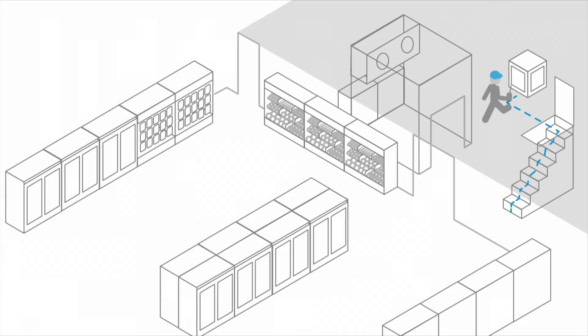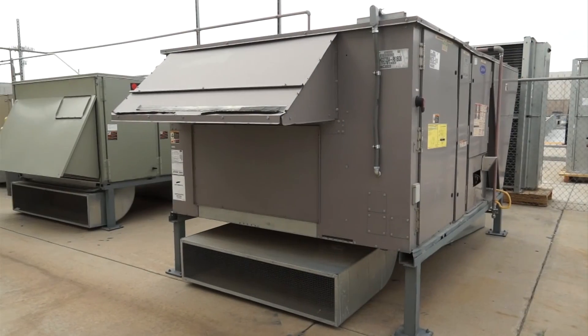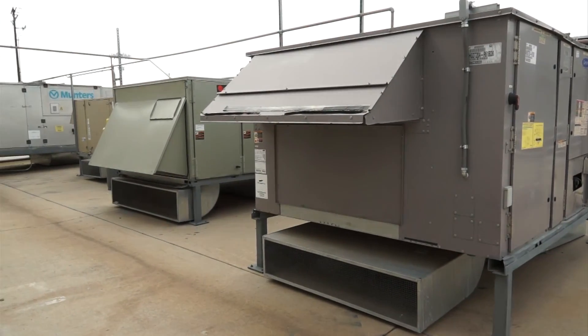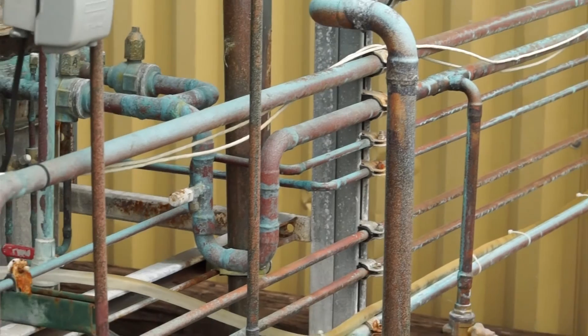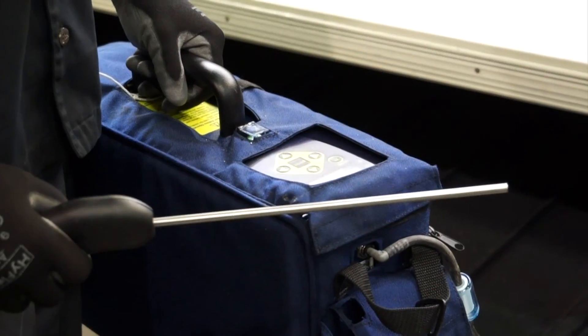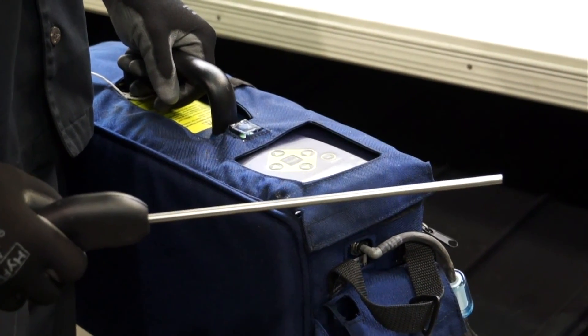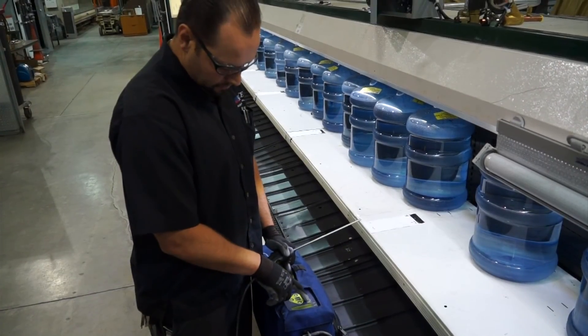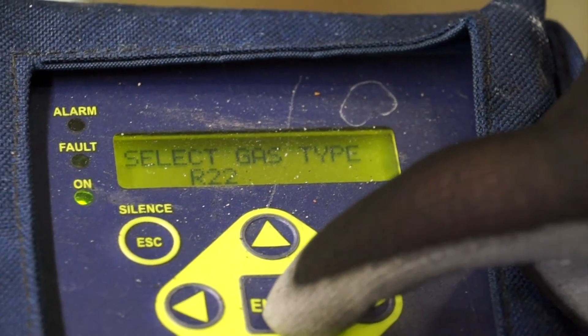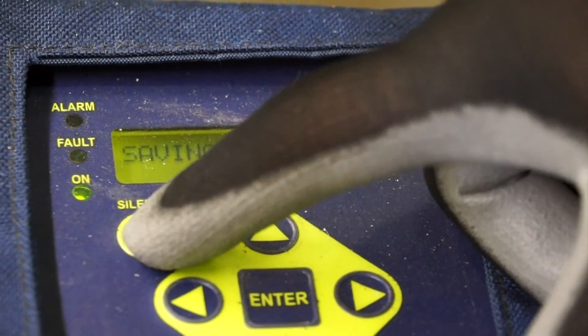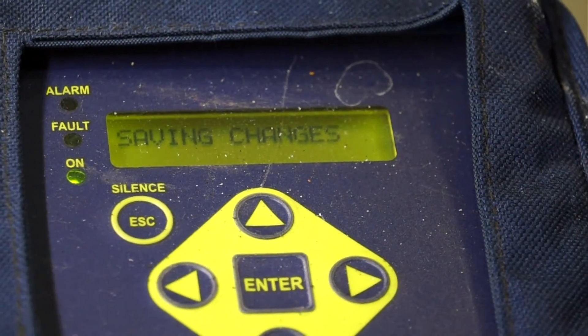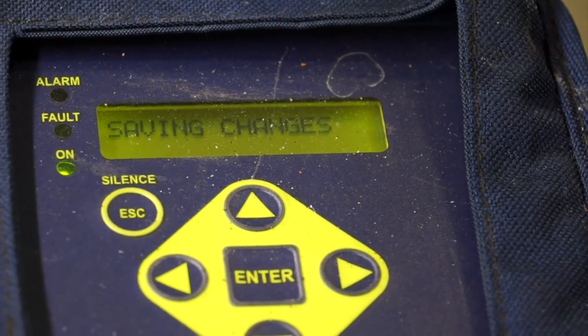Proceed to the roof equipment area. Locate equipment to be checked and look for oil traces and stains. Turn on the leak detector in an area without any possible refrigerant leaks and calibrate following manufacturer's instructions. It is recommended to start the inspection with the tool set to medium; the tool can be adjusted once a leak is found.